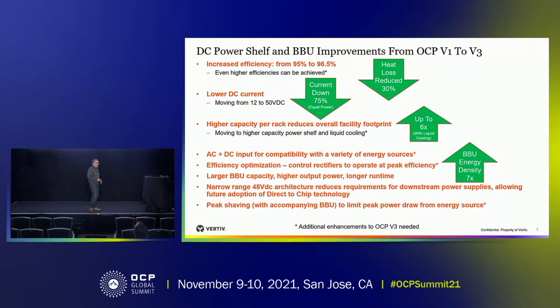Now let's talk about what this means in general numbers. I'll take you through some reduction numbers we estimate for implementing this. As I mentioned, it's about the losses. If you move from 95% to 96.5%, it doesn't seem like a big percentage increase, but that really equates to a 30% power loss reduction. If you now have a lower DC current, like moving from 12 volts to 50 volts, that's down 75%. Combining the two, you start building a really good sustainability story.